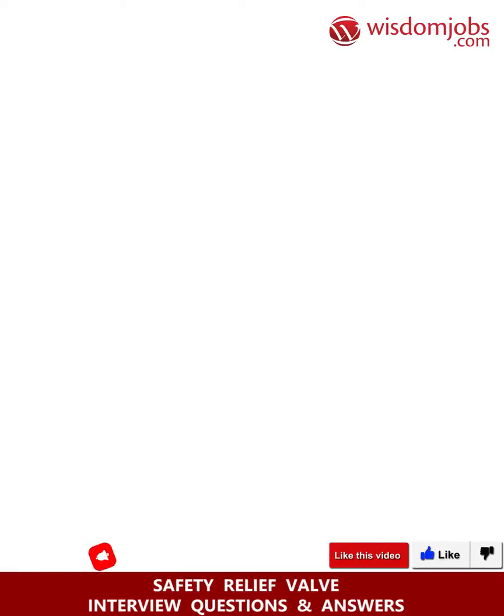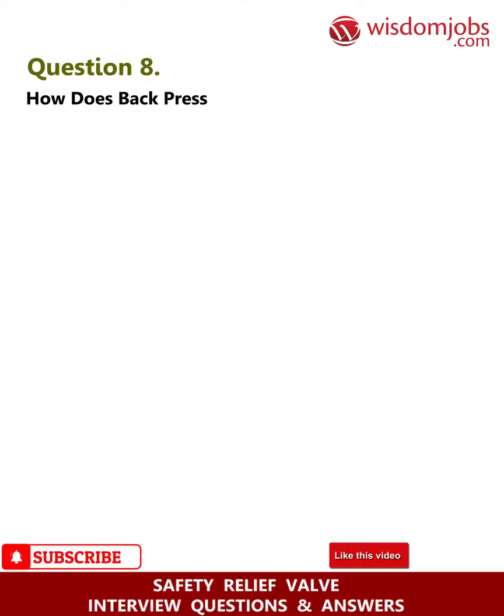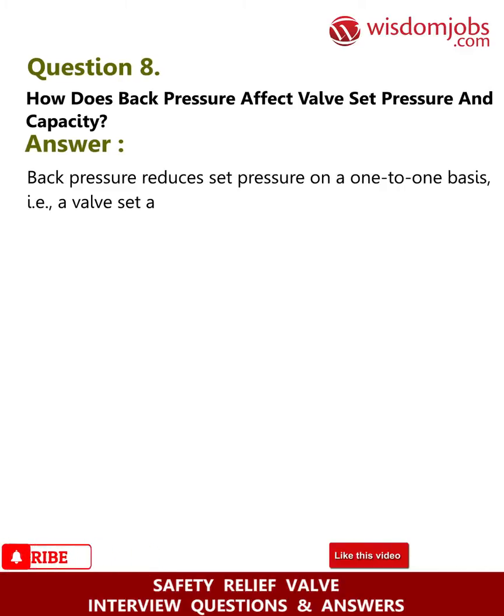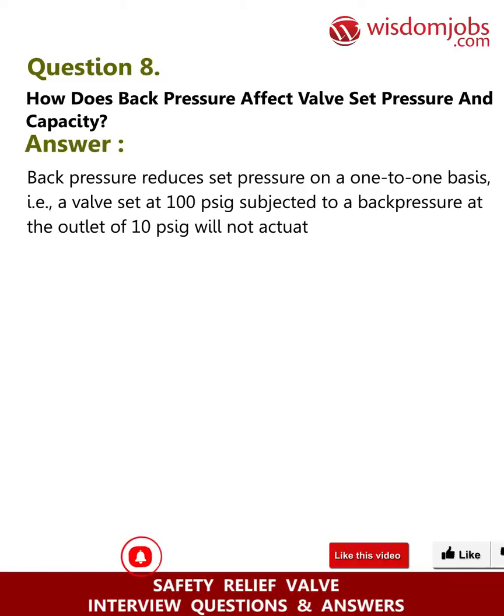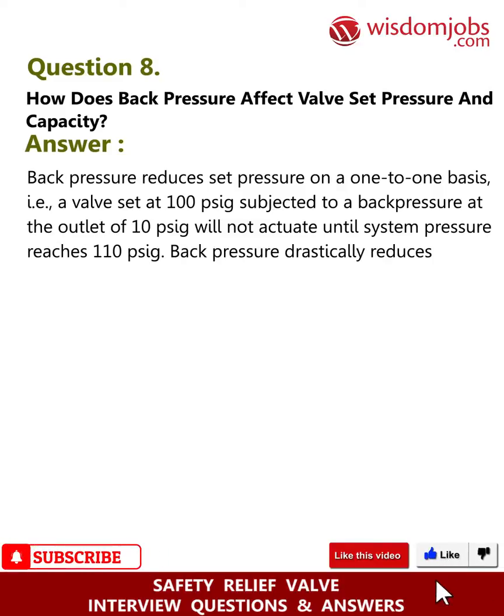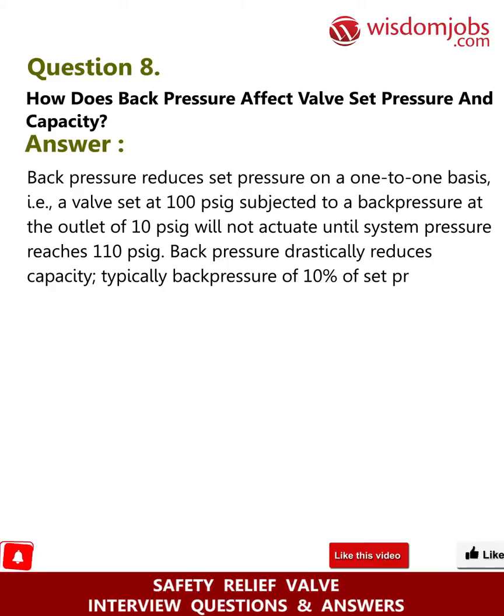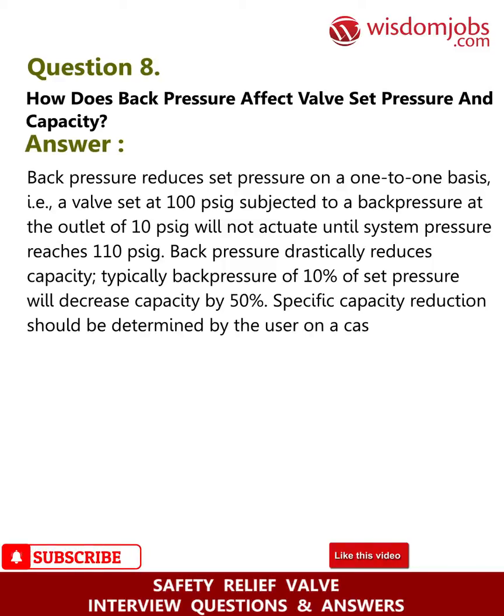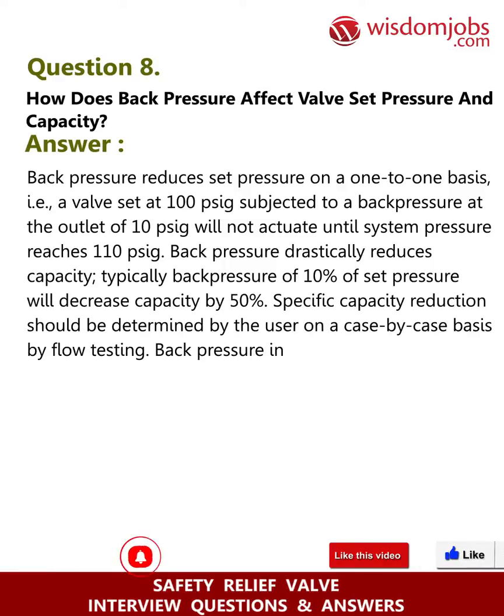Question 8: How does back pressure affect valve set pressure and capacity? Answer: Back pressure reduces set pressure on a one-to-one basis — i.e., a valve set at 100 PSIG subjected to a back pressure at the outlet of 10 PSIG will not actuate until system pressure reaches 110 PSIG. Back pressure drastically reduces capacity; typically back pressure of 10 percent of set pressure will decrease capacity by 50 percent. Specific capacity reduction should be determined by the user on a case-by-case basis by flow testing. Back pressure in excess of 10 percent of set pressure is not recommended.